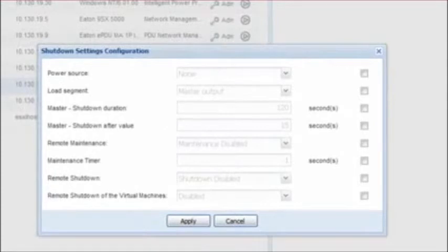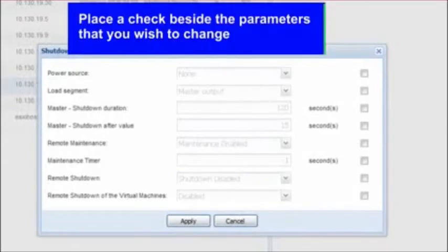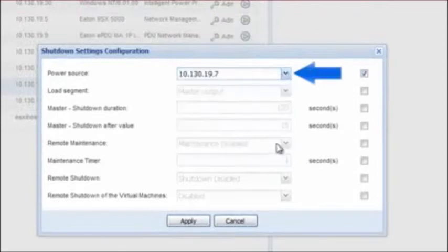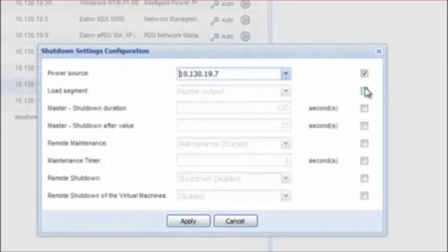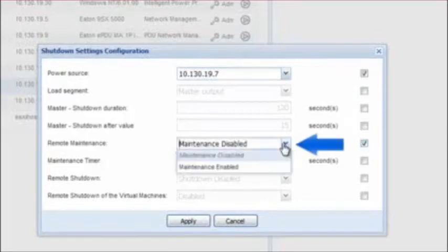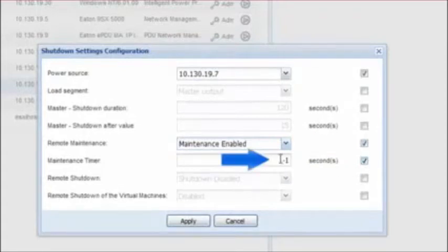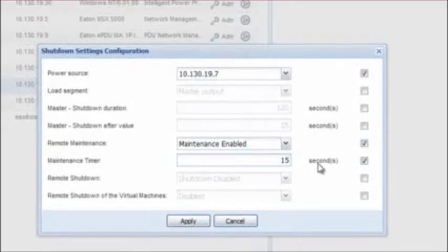The parameters selected will enable IPM to take action and trigger maintenance mode. The maintenance configuration will need the following parameters set. Power Source: select the IP address of the UPS which powers your host. Load Segment: designate the output receptacle which the host node is connected to on the UPS — typically this will be the master segment. Remote Maintenance: enable this option to grant IPM permission to trigger the maintenance mode and migrate VMs from the selected host to the other available hosts. Maintenance Timer: enter an amount of time in seconds which will dictate the length of time IPM will delay sending the signal to enter maintenance mode and begin migrating virtual machines from the designated host. Click Apply to activate the settings.